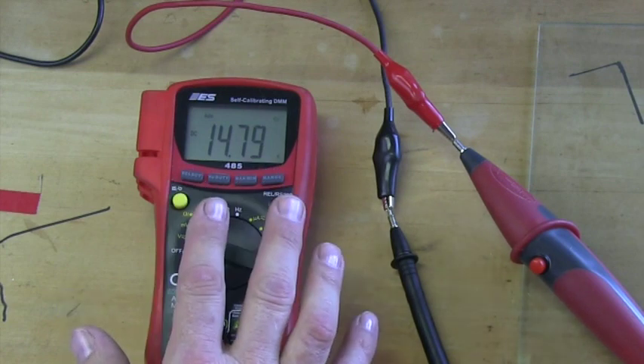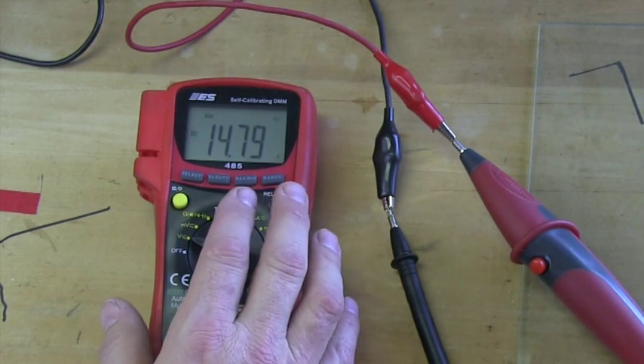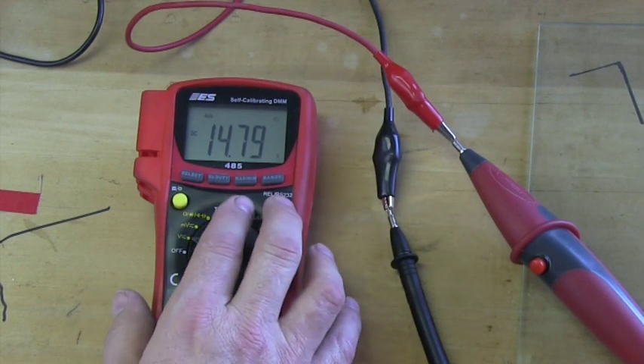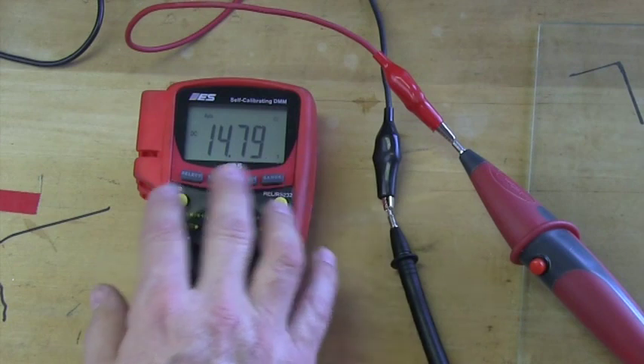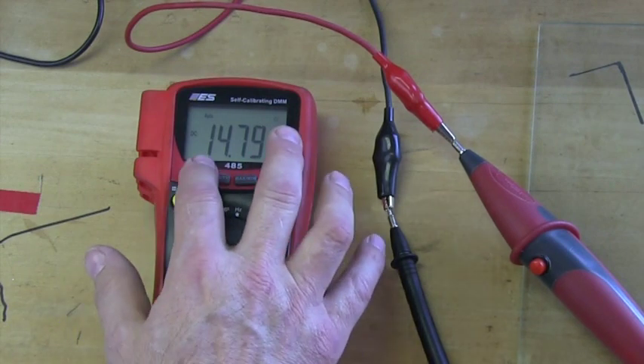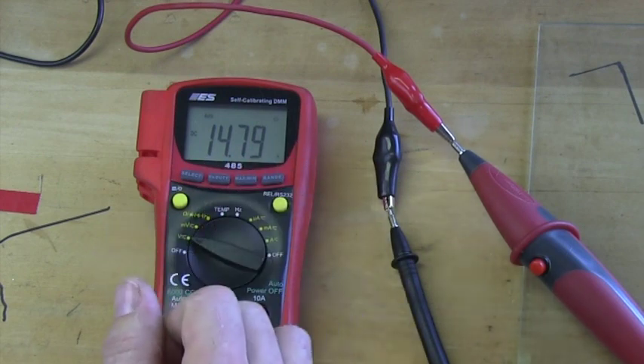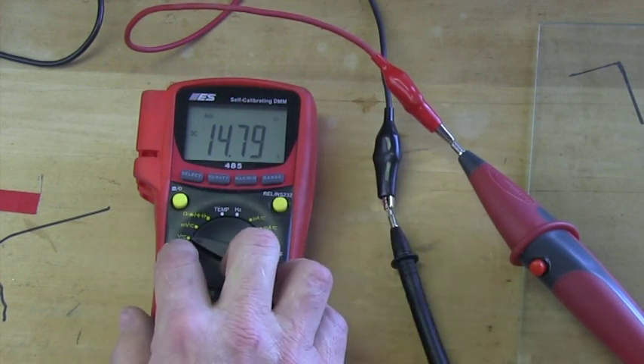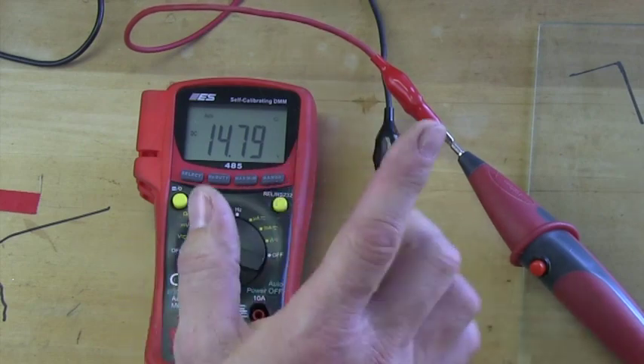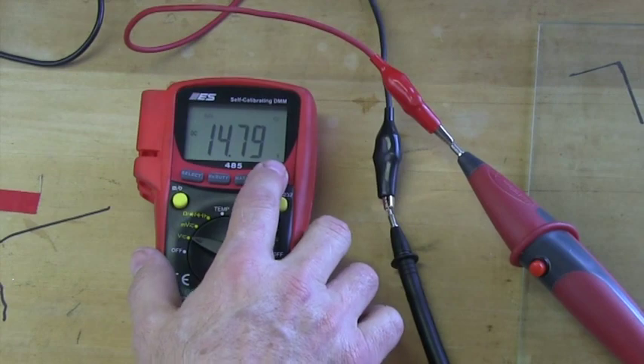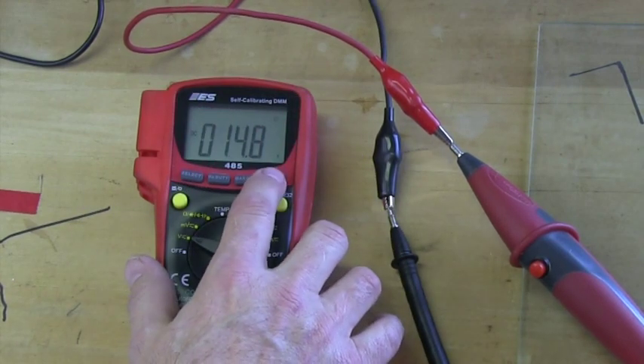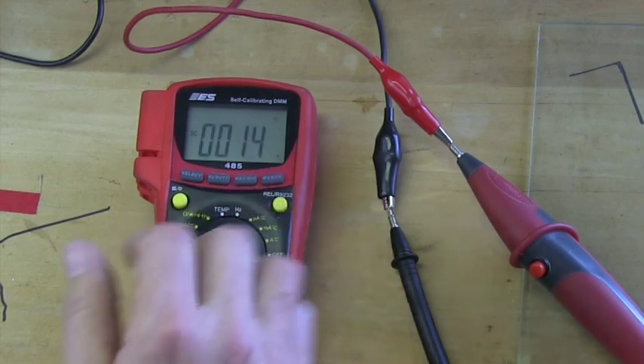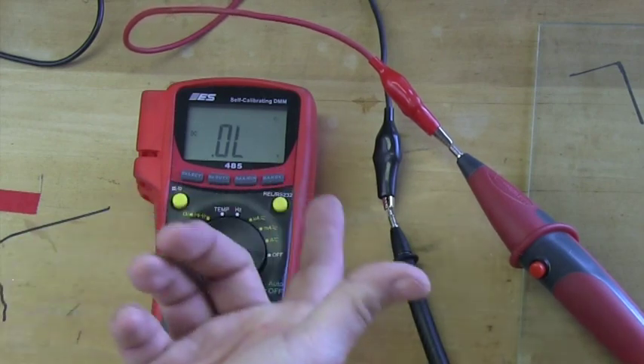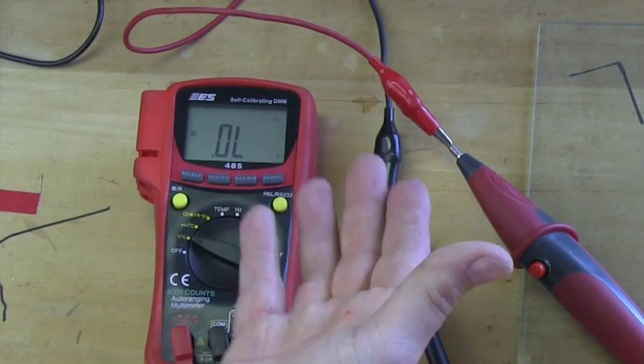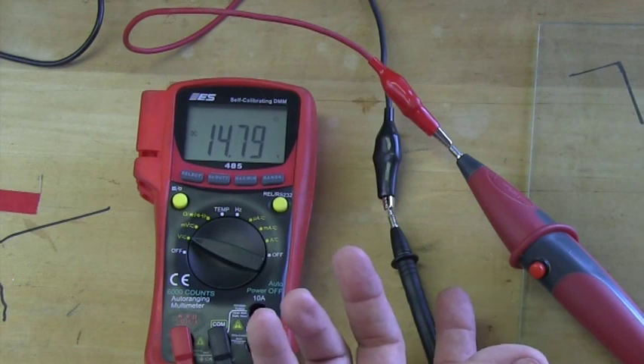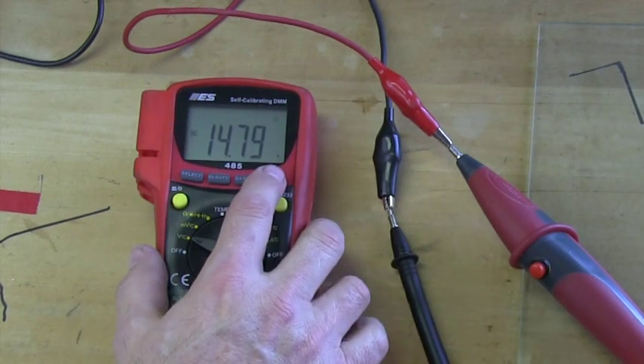This meter, the 485, is very, very accurate, especially with the calibration feature in it. So make sure that you always read the exact number, because that helps you with diagnostics. There's a difference between 14.79 and 14.69. There's a difference. Okay, so on the voltage scale, if we hit the range button, which I recommend you do not do, you'll notice that we lose the auto feature, but then we get the 14.8. Now we get 14. Now we're going to get OL because we're trying to read on a scale that's too low. So then we come back up one. We're at 14.79 again.